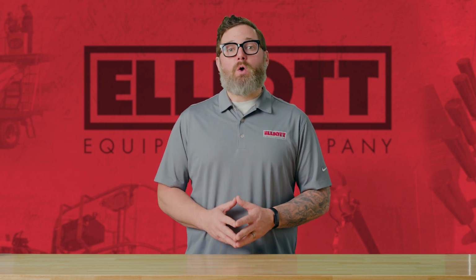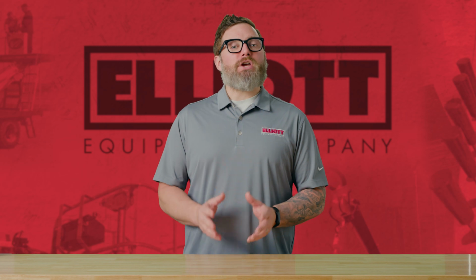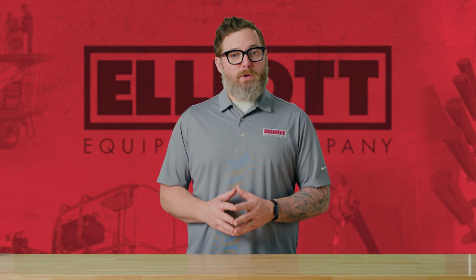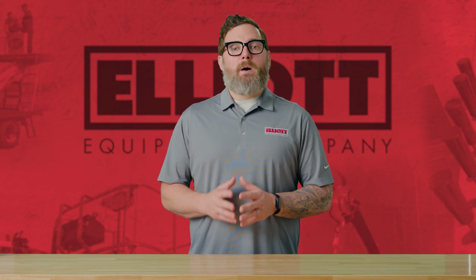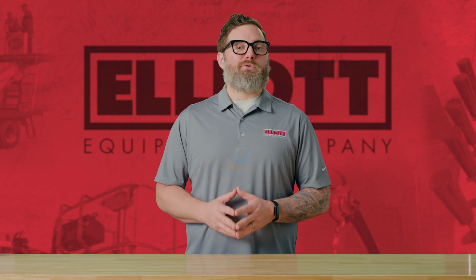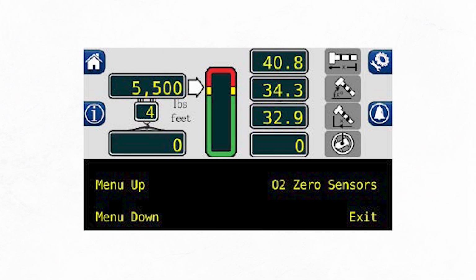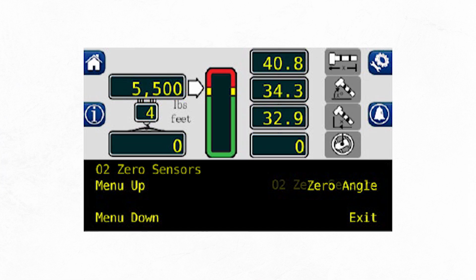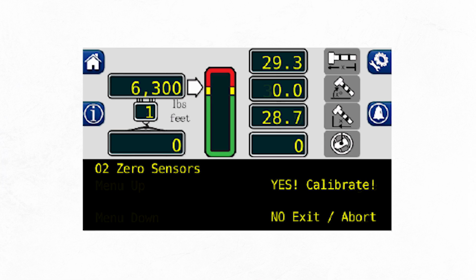Double check this measurement with a digital level. Then check the voltage between the blue wire and the green wire. It should measure between 0.400 and 0.600 volts in the right position. Next, you're going to enter the 02 Zero Sensors menu. Press the menu up button to display 0 angle and click on the 0 angle button. Finally, press Yes Calibrate to complete the routine.